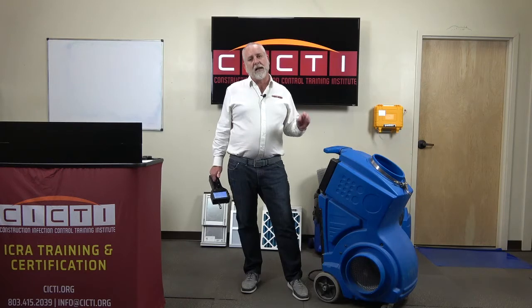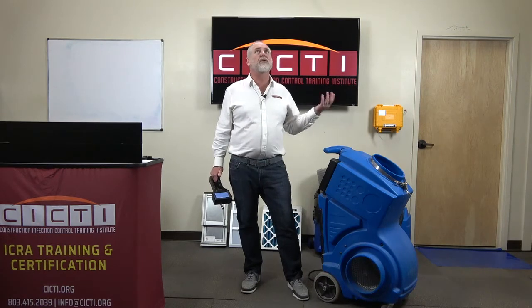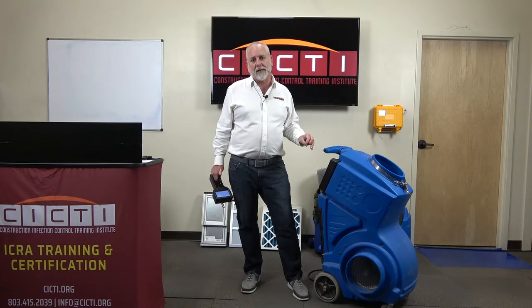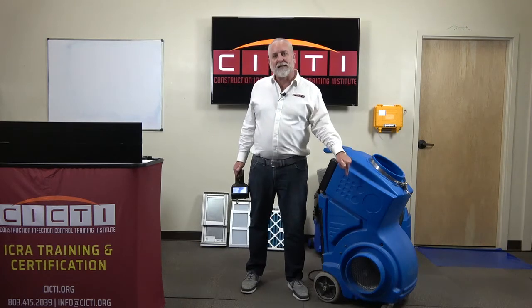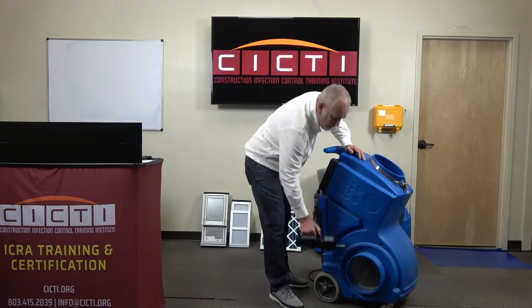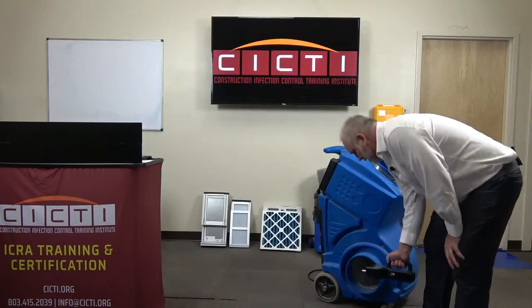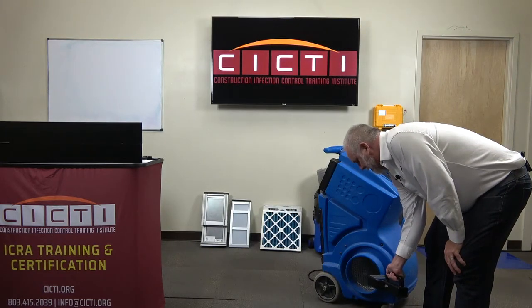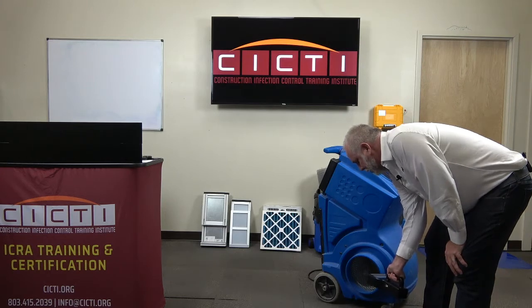I know the filter is rated at 99.97% efficiency, but that's more in controlled environments. This is the real world. If I can demonstrate 99%, that tells me that the gasket is properly engaged, that the filter was properly installed and is doing its job. Okay, so let's put this to the test. Let's look for a value of 153 or less, because I had 15,301 going in.